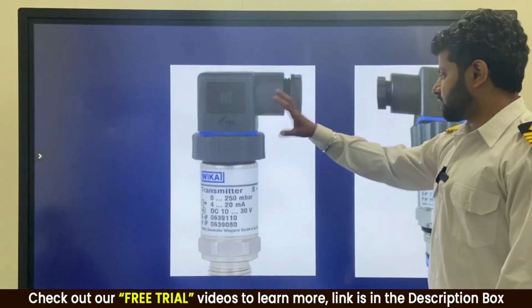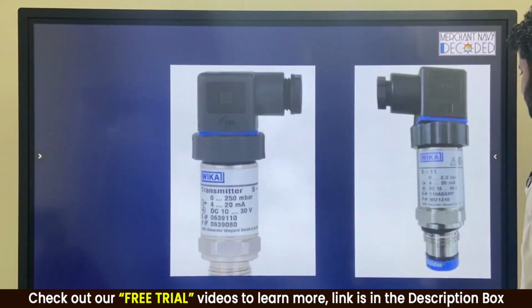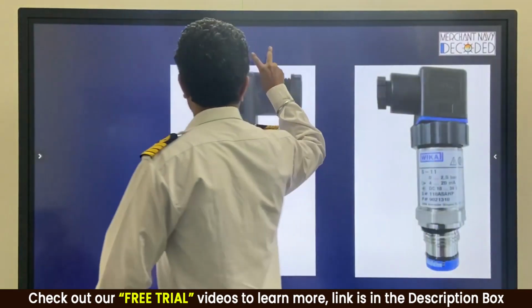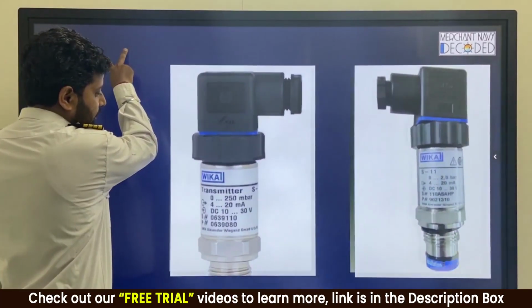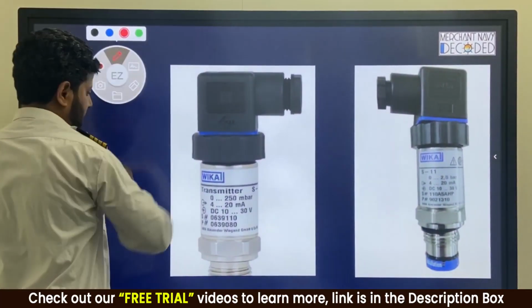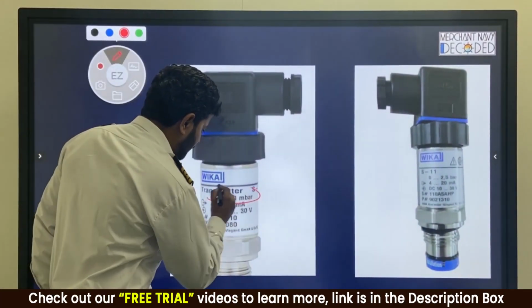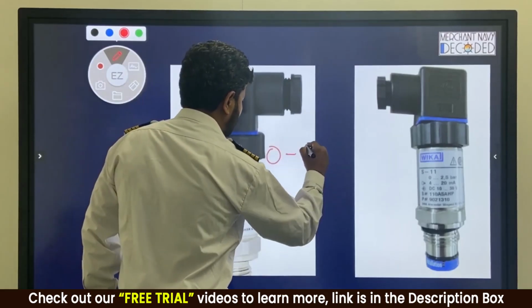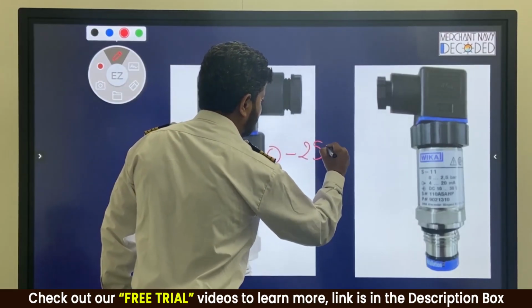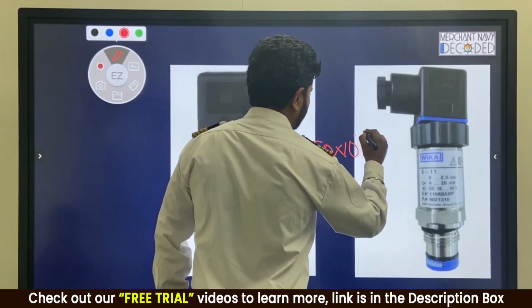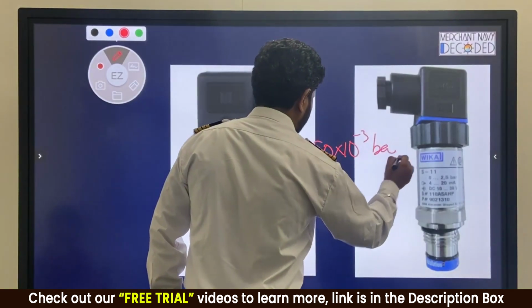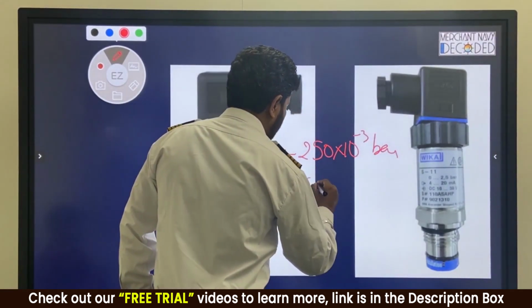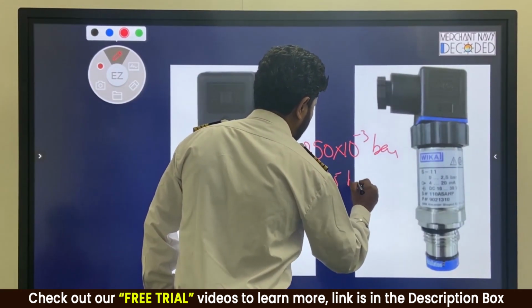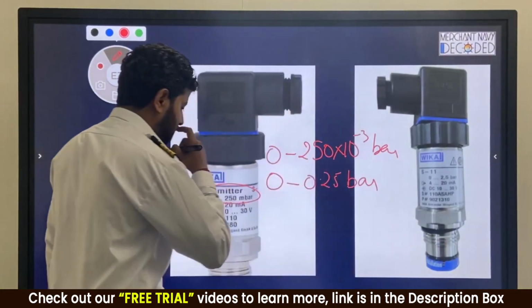This is your pressure transmitter. Can you see over here? So now in this pressure transmitter, you will see a very good thing, and that is this is your range, 0 to 250 millibar. That means 10 to the power minus 3 bar. This is the range. That means 0 to 0.25 bar. Very slow, 0 to 0.25 bar.